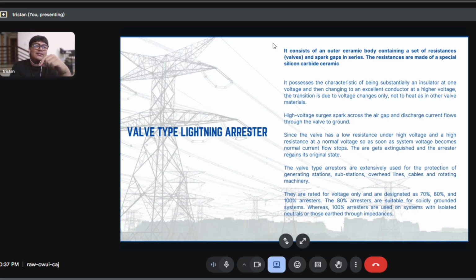So gamit siya mostly sa mga station, sa lahat. Sa mga data nakikita natin, gamit siya. So they are rated for voltage only and are designated as 70%, 80, and 100% arrestors. The 80% arrestors are suitable for solidly grounded systems, whereas 100% arrestors are used on systems with isolated neutrals or those earth through impedances.